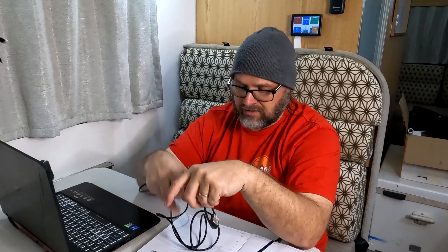I've got the laptop set up and ready to go. With your smart products — Smart Solar, Smart Shunt, Smart Orion, etc. — there are two ways to program them. You can use the Victron Connect app via Bluetooth, pairing directly to the device. If you don't have Bluetooth, the other way is with a VE.Direct to USB adapter — about 20 or 30 bucks — with USB one end and a VE.Direct cable the other. Plug it into your device and laptop, then use the Victron Connect app on your laptop. Just note that not all smart products have the VE.Direct plug — the Smart Orion doesn't, the Smart Battery Protect doesn't, but the Smart Shunt and Smart Solar do.